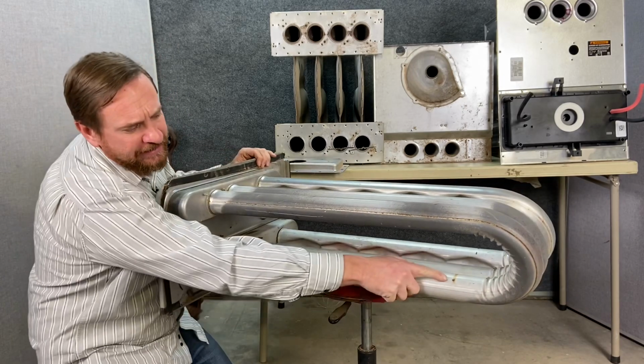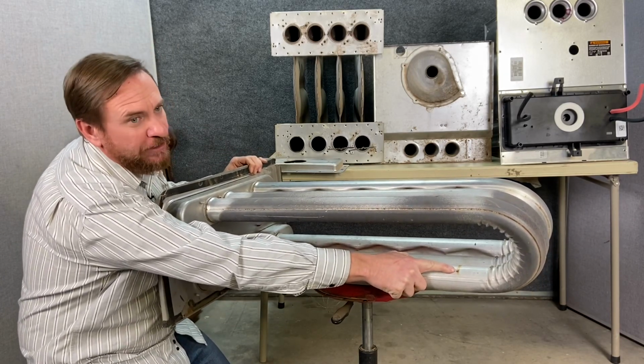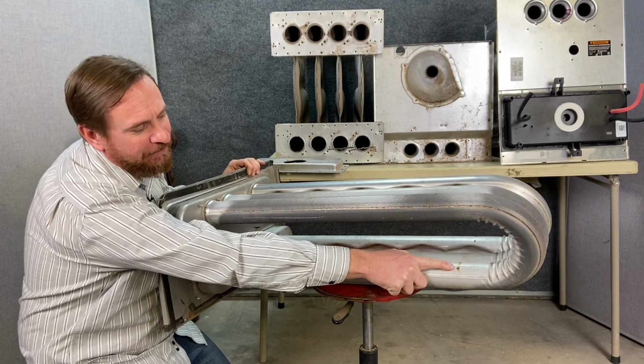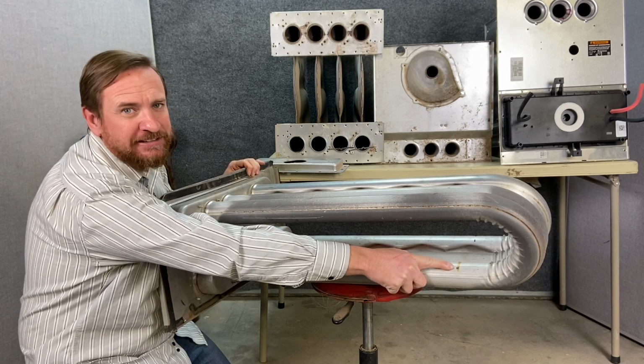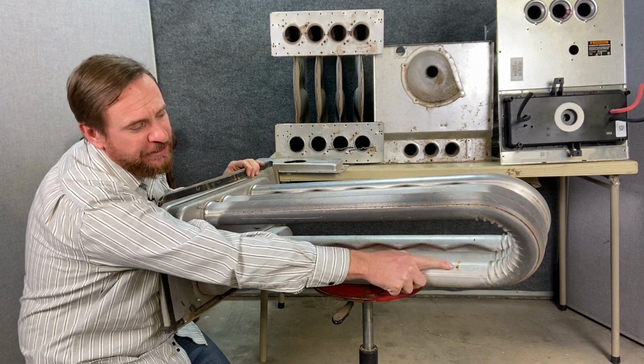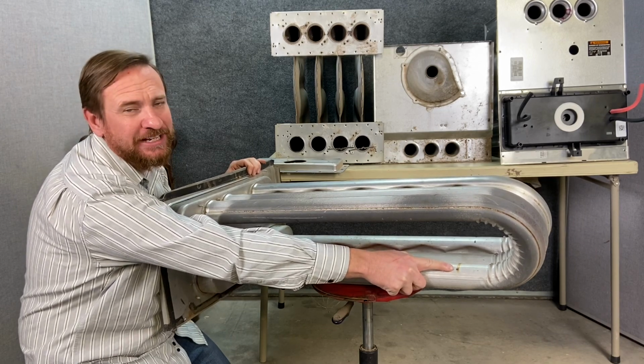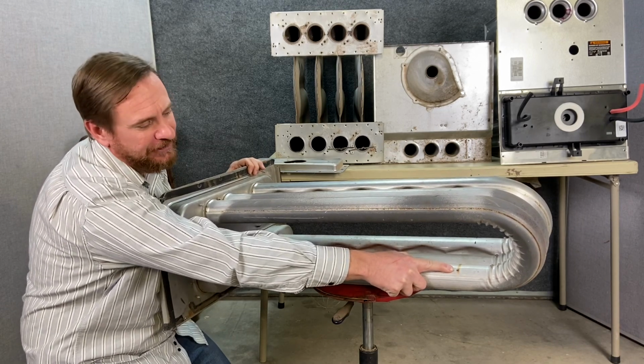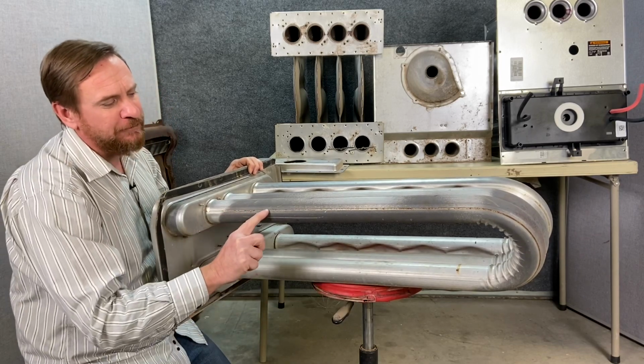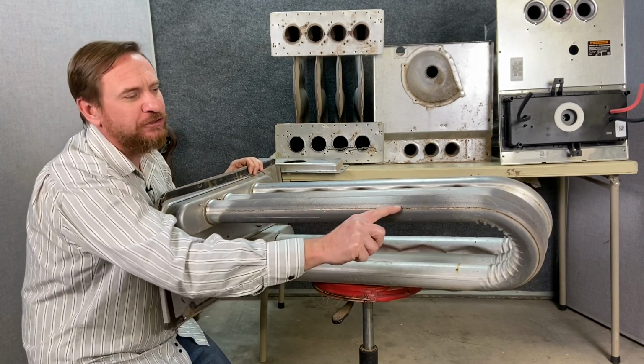Also, I want to point out these rust spots here. These rust spots are an important thing we want to look for. A little spot of rust like this can create a hole in the heat exchanger. This was most likely leaking combustion gases and carbon monoxide into the building. These seams where these pipes were put together are also another place these are notorious for leaking.